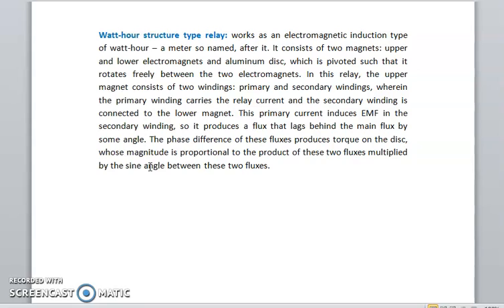This primary current induces EMF in the secondary winding, so it produces a flux that lags behind the main flux by some angle. The phase difference of these fluxes produces torque on the disk, whose magnitude is proportional to the product of these two fluxes multiplied by the sine of the angle between these two fluxes.